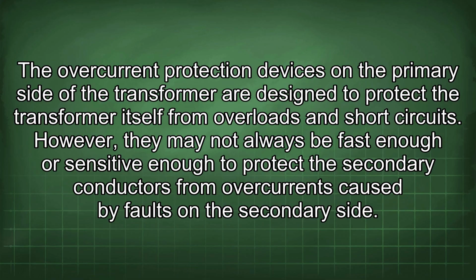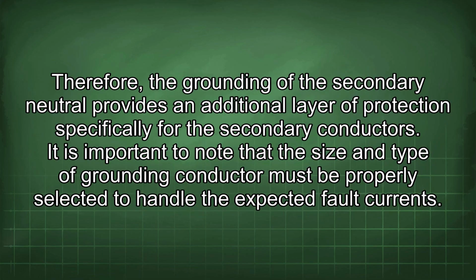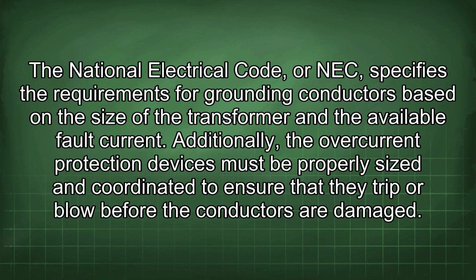The overcurrent protection devices on the primary side of the transformer are designed to protect the transformer itself from overloads and short circuits. However, they may not always be fast enough or sensitive enough to protect the secondary conductors from overcurrents caused by faults on the secondary side. Therefore, the grounding of the secondary neutral provides an additional layer of protection specifically for the secondary conductors. It is important to note that the size and type of grounding conductor must be properly selected to handle the expected fault currents. The National Electrical Code, or NEC, specifies the requirements for grounding conductors based on the size of the transformer and the available fault current.